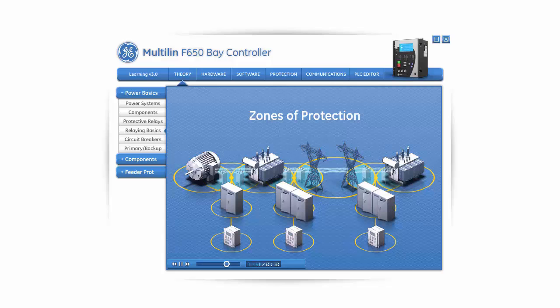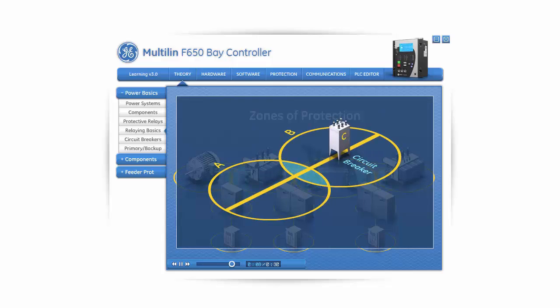If the zones of protection are set up such that overlap occurs on only one side of the breaker, the relaying equipment of the zone that overlaps the breaker must also be able to trip the breakers in the neighboring zone in order to completely disconnect faults in certain areas. This can be illustrated in the following example. For a fault located as shown, the circuit breakers of Zone B will trip, but because the fault is outside of Zone A, the relaying equipment of Zone B will need to send a trip signal to the breaker in Zone A. A potential drawback of this is that the breaker in Zone A will be tripped unnecessarily for faults occurring in Zone B to the right of breaker C.